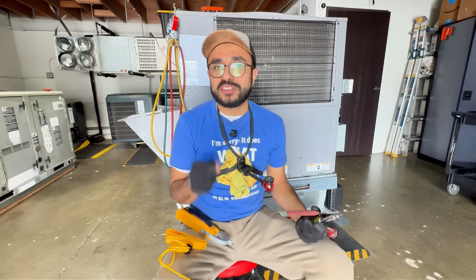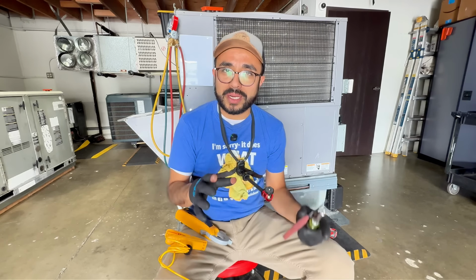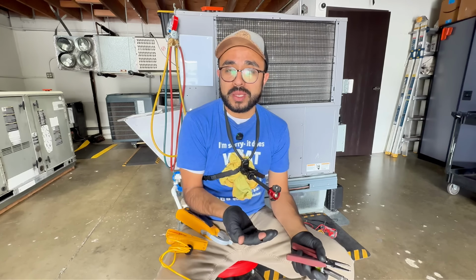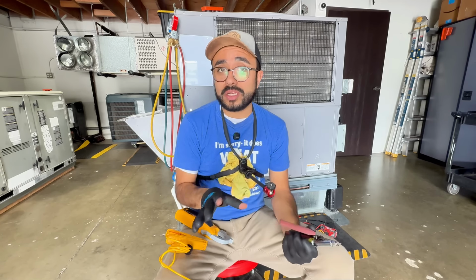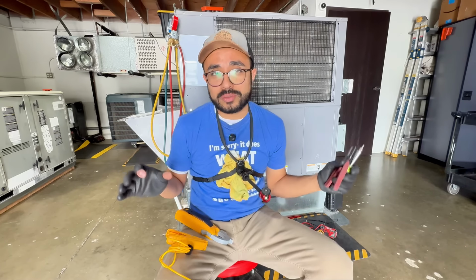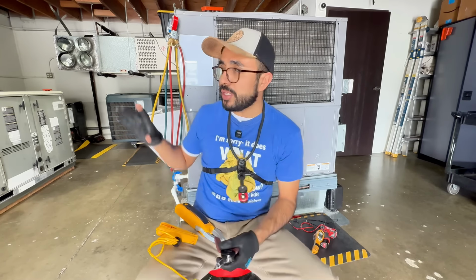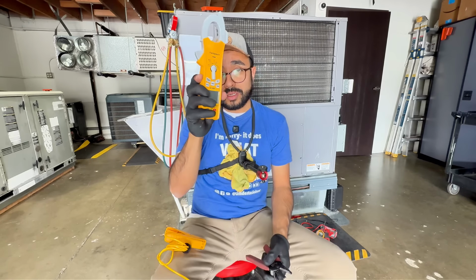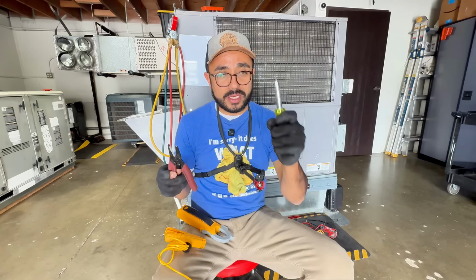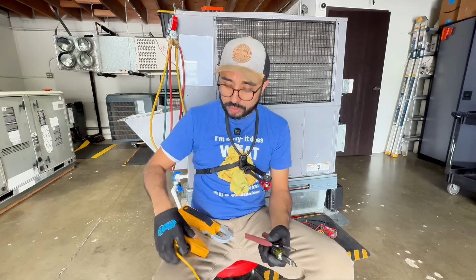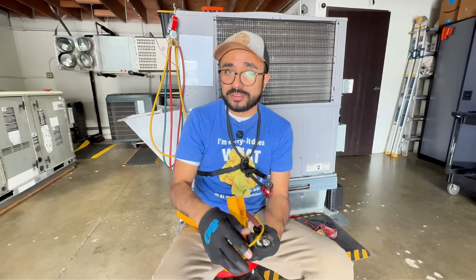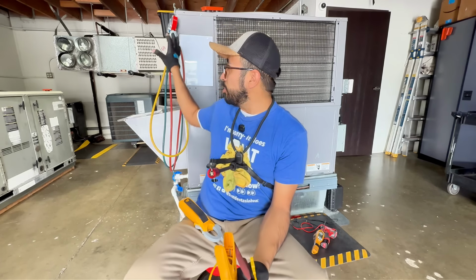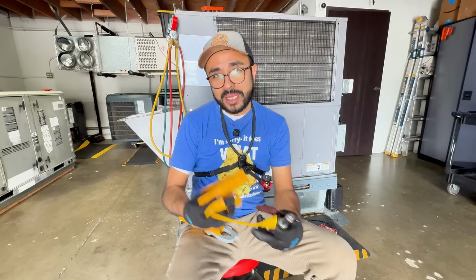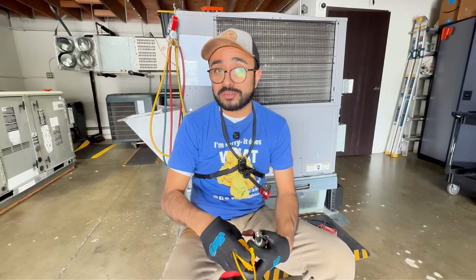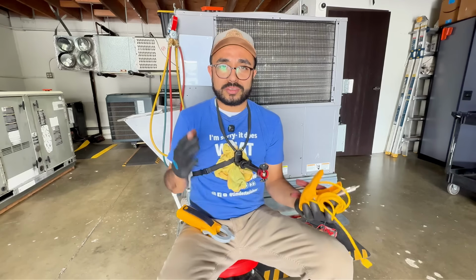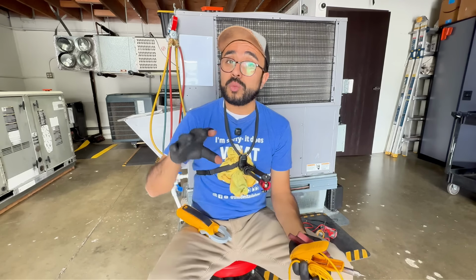Hey friends, in today's video we're going to be focusing on the troubleshooting mindset behind a service call. Now I once heard someone say that all you need is 4 tools to figure out any service call for any unit. They say you need gauges, your meter, wire strippers, and an 11-in-1 screwdriver. Now I'm also using a temperature clamp because you don't necessarily need digital gauges. We're just using regular analog gauges, but I am using the temperature clamp to read superheat and subcool. But really, all you need is just these 4 tools along with knowledge.